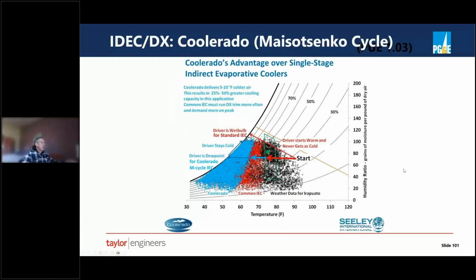Real quick, another technology out there is the Maisotsenko cycle used by the Coolerado product. I don't know a whole lot about it. It's similar to an indirect evap cooler, but instead of working off of the wet bulb condition, it works off of the dew point condition. So it has the potential to provide even more free cooling without DX. And so you could get away with even less DX trim. Of course, you need to balance that against the cost of this equipment.